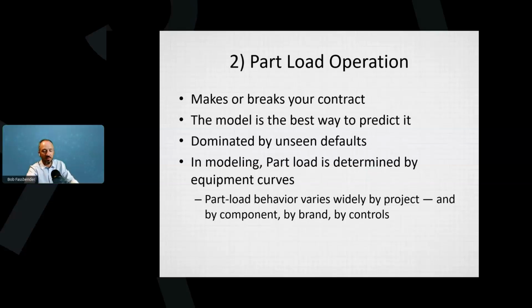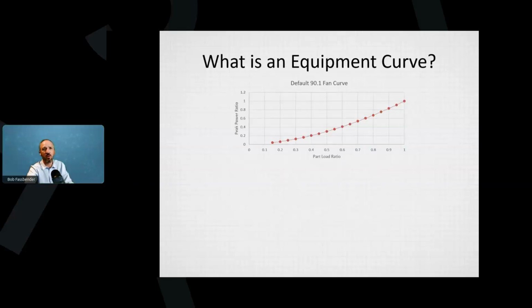But the term to learn is part load, which is determined and driven by equipment curves. An equipment curve is unique to each piece of equipment. Each one has its own equipment curve. Some of them have multiples, and it changes by brand and by controls, among a number of factors. And those are in all of the defaults that you don't realize you're setting. I'm just going to go over an example.